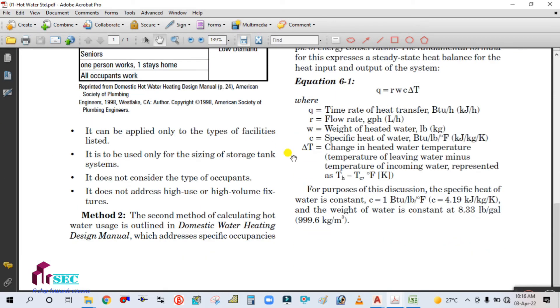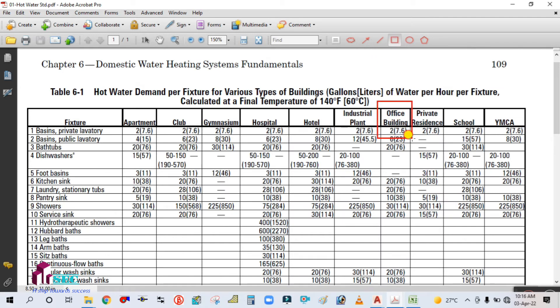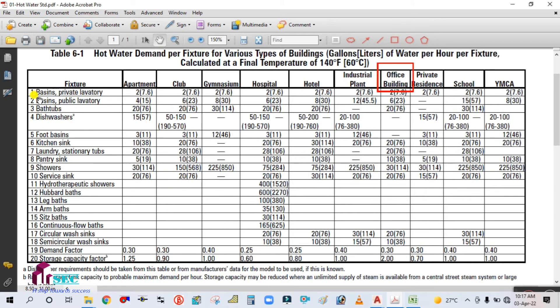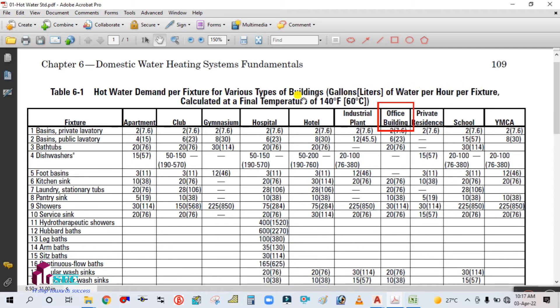For the GPH value, I use a hot water demand table that I have uploaded on my drive — please download it from there. Find your building type — office building — and look for the lavatory fixture. This is Table 6-1: 'Hot water demand per fixture for various types of buildings — gallons of water per hour per fixture, calculated at a final temperature of 140°F (60°C).' Outside the bracket is gallons; inside the bracket is liters per hour per fixture.